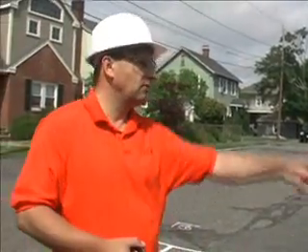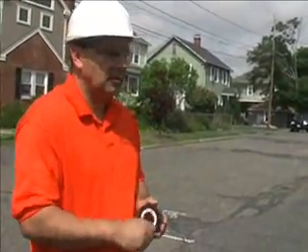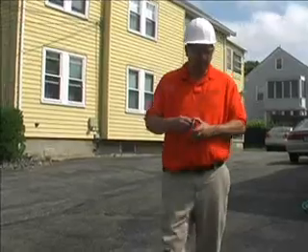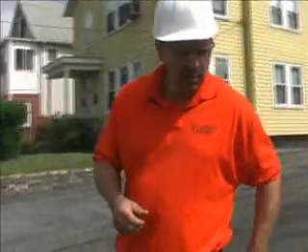You have a service line that runs right up the side here. So there's all kinds of things here. This is definitely a grade 2 leak. And the grade 2 means that it's a potential hazard? Potential future hazard requiring monitoring until the leak is repaired. Here's the leak. We can finish this up with a few measurements.